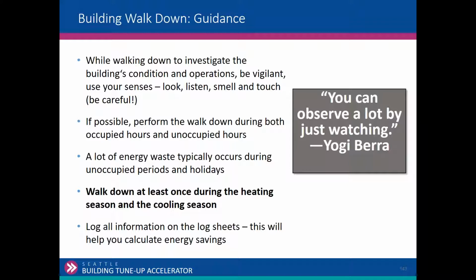Also, figuring out what happens in the transition. What happens when we go from unoccupied to occupied, that warm-up cycle? What's on? Where's my outside air damper position? What are my exhaust fans doing? And then also in that transition from occupied to unoccupied, am I doing optimum start? Am I keeping the HVAC on till midnight for the custodial crew? So looking at both of those transitions.